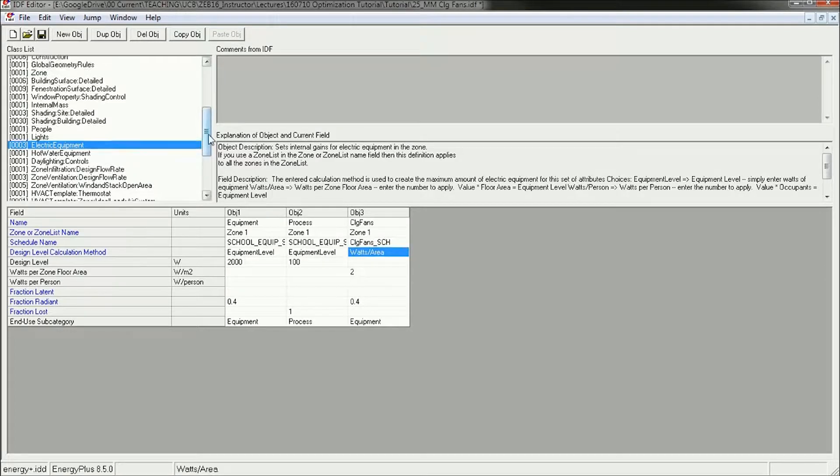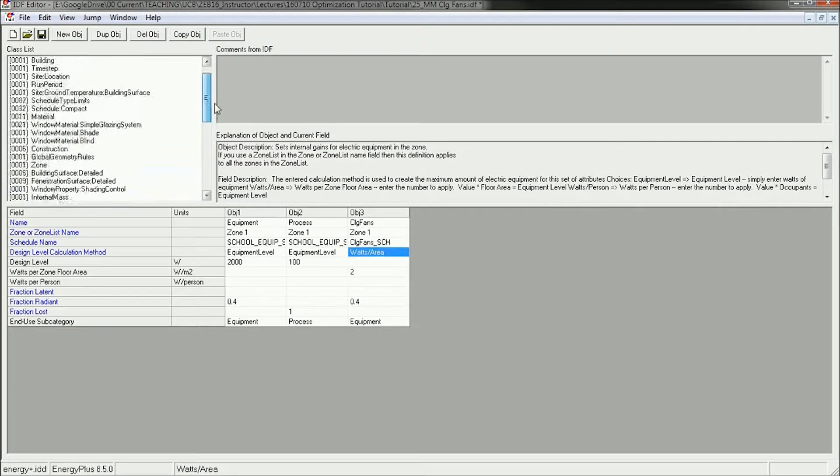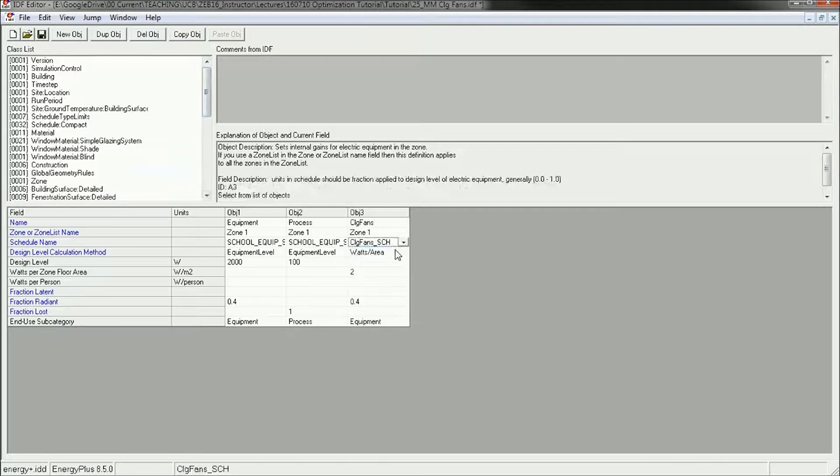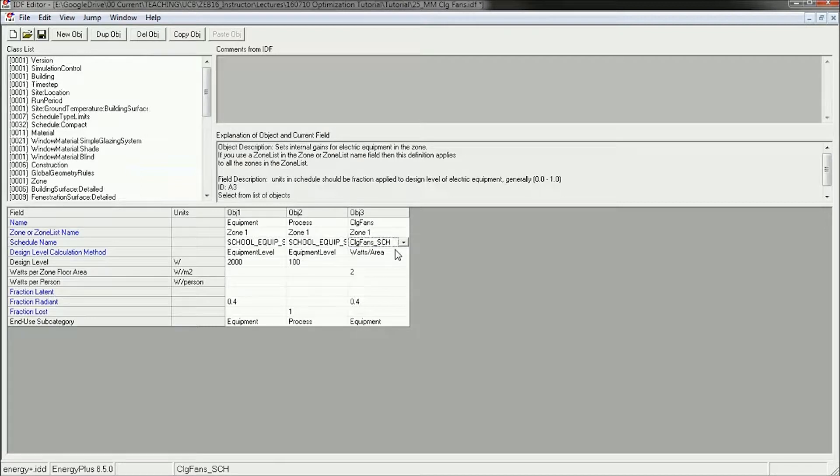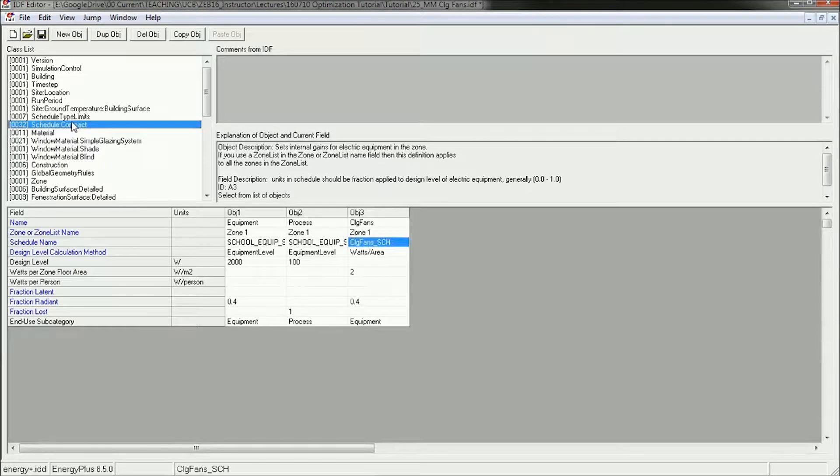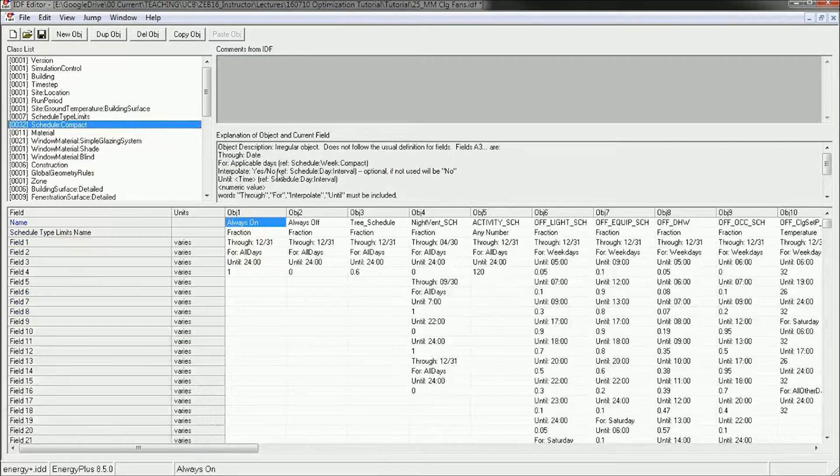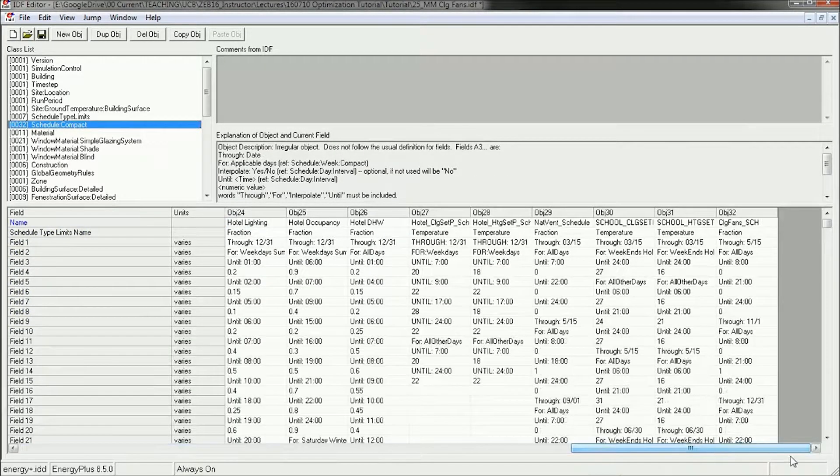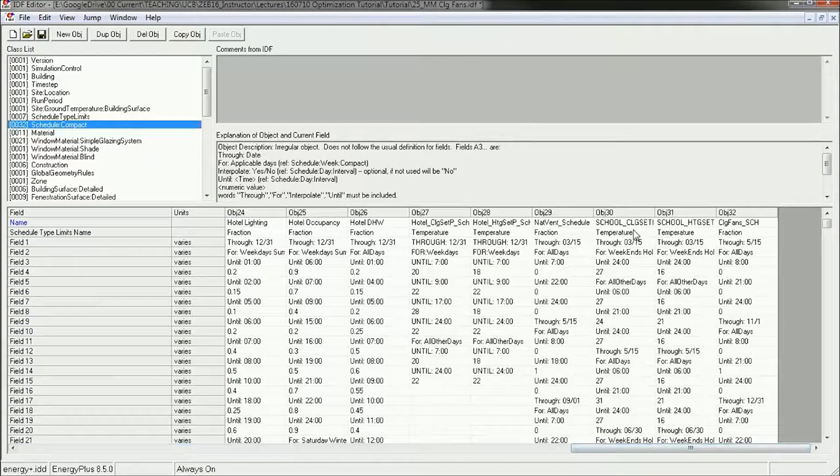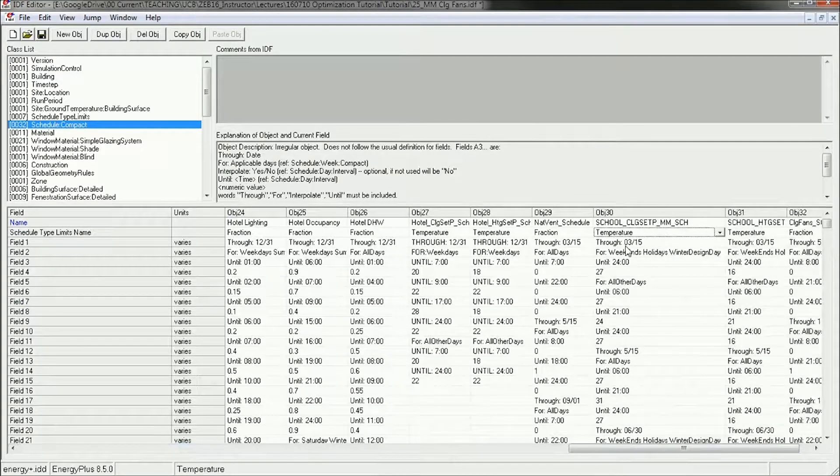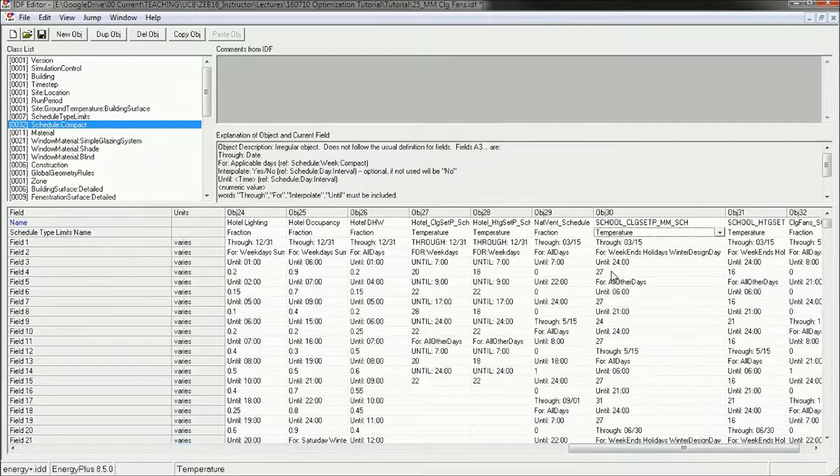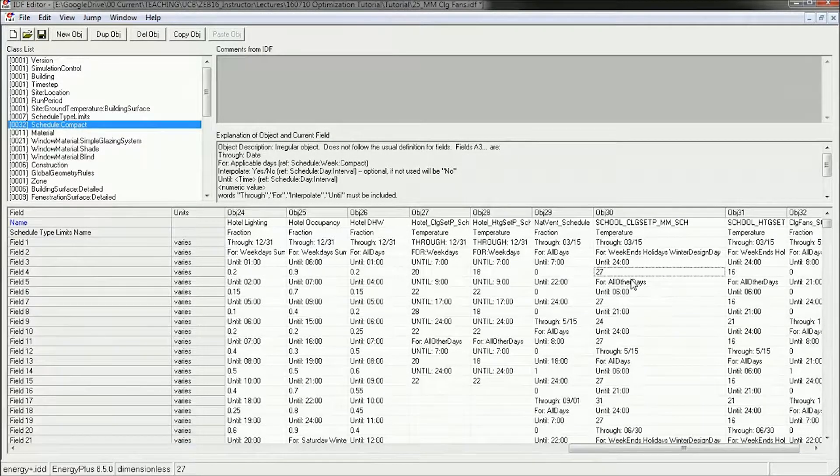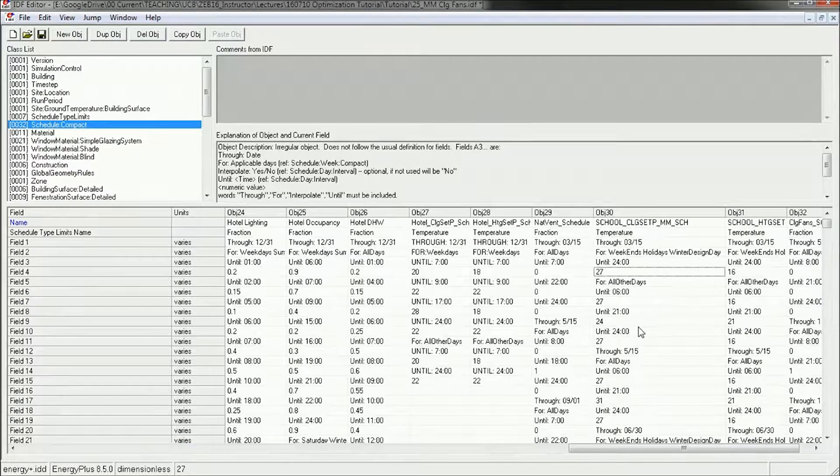The only thing left to do then is to increase the cooling set points accordingly so we get another 2 degrees Celsius of perceptual cooling from the ceiling fans. So whenever we've got the cooling system on, we can take advantage of those ceiling fans, that air movement, and increase that set point.